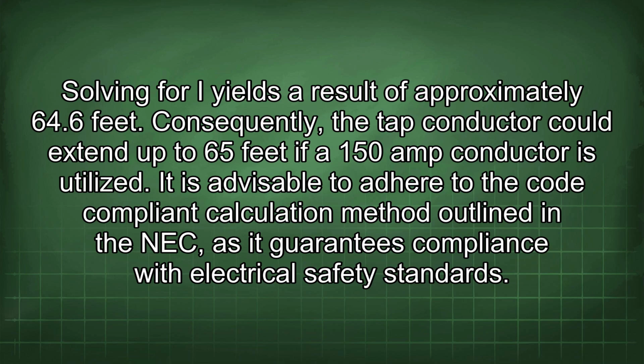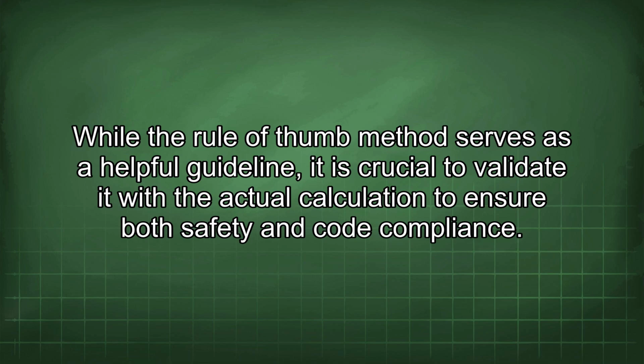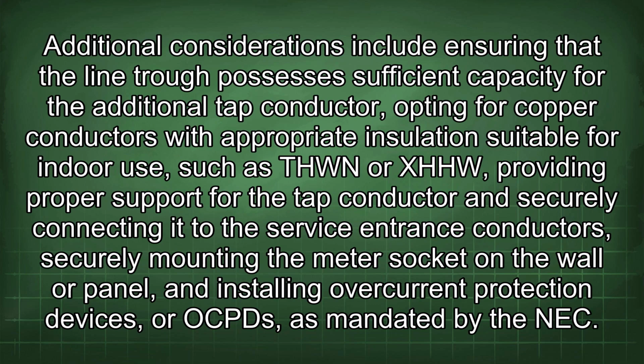It is advisable to adhere to the code-compliant calculation method outlined in the NEC, as it guarantees compliance with electrical safety standards. While the rule of thumb method serves as a helpful guideline, it is crucial to validate it with the actual calculation to ensure both safety and code compliance. Additional considerations include ensuring that the line trough possesses sufficient capacity for the additional tap conductor, opting for copper conductors with appropriate insulation suitable for indoor use, such as THWN or XHHW, providing proper support for the tap conductor and securely connecting it to the service entrance conductors, securely mounting the meter socket on the wall or panel, and installing overcurrent protection devices, or OCPDs, as mandated by the NEC.